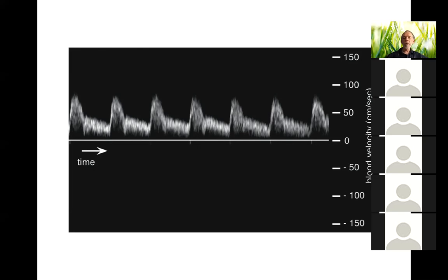Now, I mentioned the limits. If you imagine that we had a high Doppler shift that actually exceeded the limits, we would have a problem. That's a particular artifact known as frequency aliasing that we'll cover in detail next term. But there's a very, very simple thing that can be done about this, and that is that the baseline of the Doppler display doesn't have to be in the center.